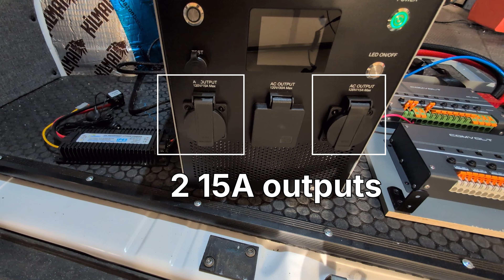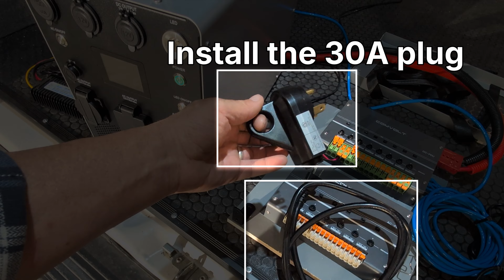The main power system has two 15 amp outputs, which would plug in directly to the PDU, but that would further limit those 8 circuits to a total of 15 combined amps. There's also a 30 amp output on the main unit, but you have to figure out how to plug that into this PDU. So that's where the 30 amp detached plug comes in. The instructions indicate that you should cut the end off of the wire that came with the PDU and install this 30 amp plug onto that wire.